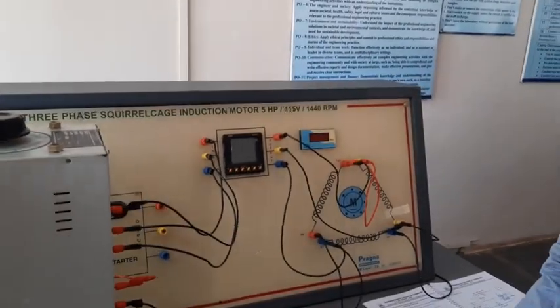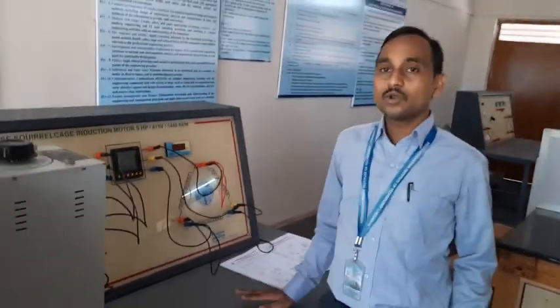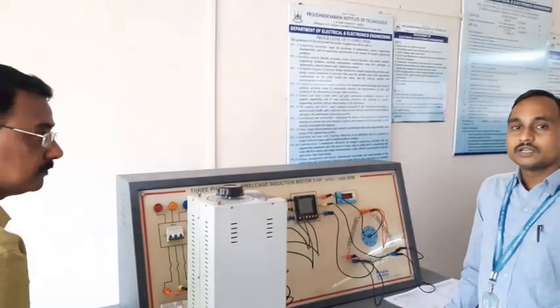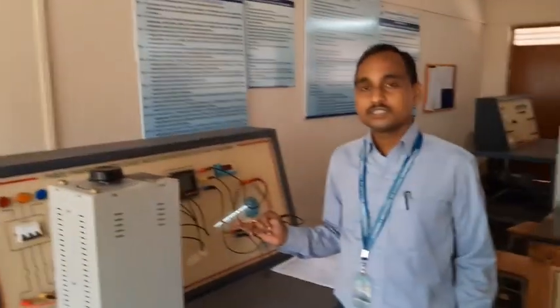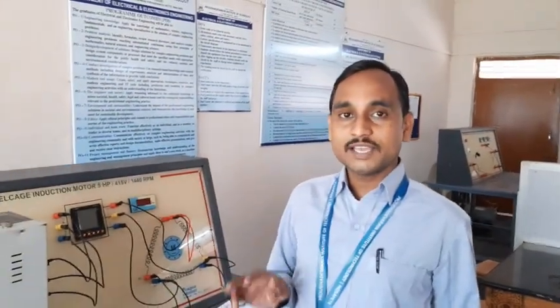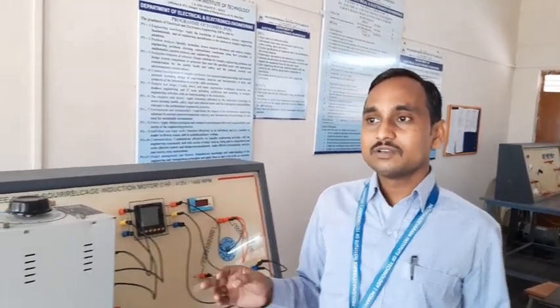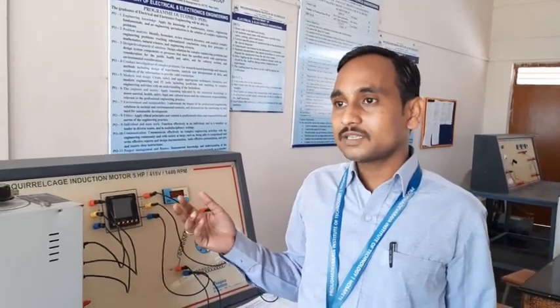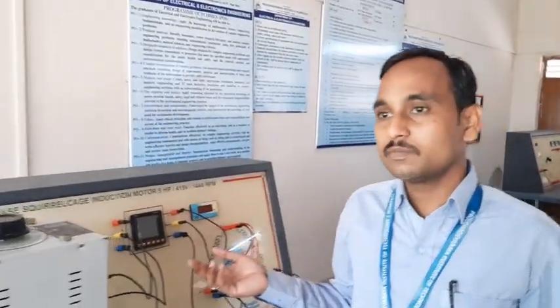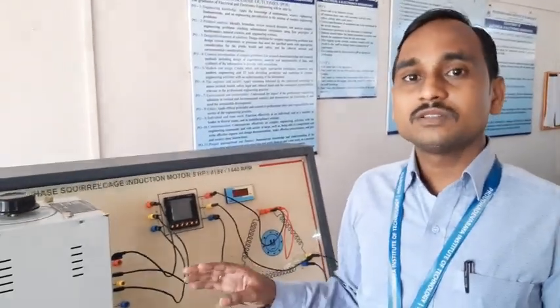After taking the readings of the no load test and blocked rotor test, you will get V0, I0 and W0, and similarly VSC, ISC and WSC. These readings are very helpful for constructing the circle diagram of an induction motor. We require a circle diagram because it explains the total characteristics of the induction motor, like the speed-torque characteristics and the performance of the induction motor, which can be noted by means of the circle diagram.